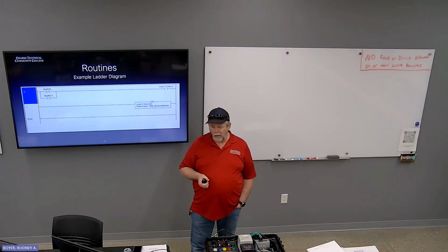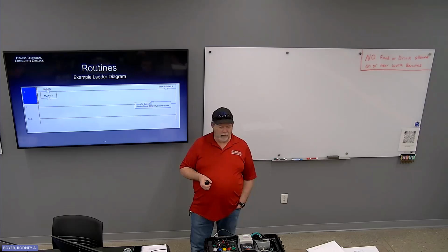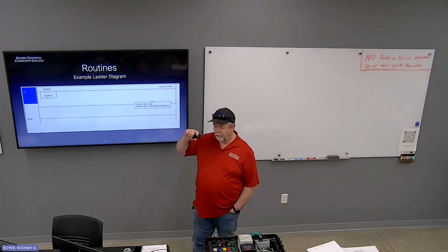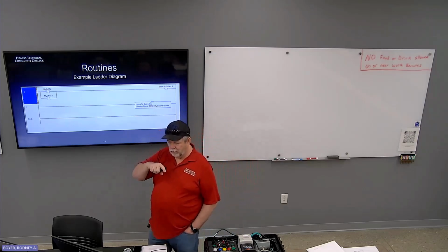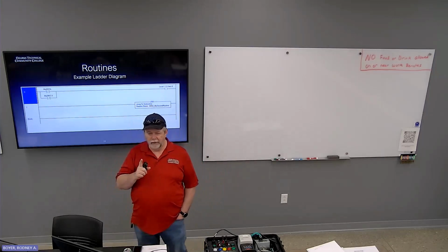If you need a whole bunch of the same type of off and on, then rather than creating a whole bunch of bools, you just create a DINT, INT, whatever you need, and then individually address the bits. So it just depends what you're trying to do. But what you have to remember, like we said last week, if you are creating a bool, one bit, bit 0 is the only one that's available.